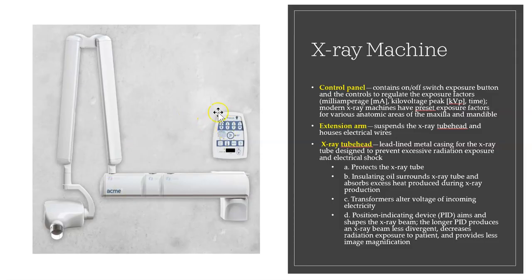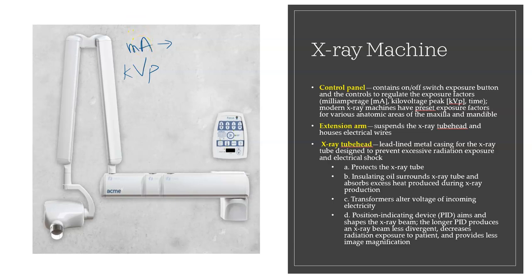When looking at the x-ray machine, there is the control panel where the on/off switch is. This is also where settings regulate exposure factors such as mA (milliamperage) and kVp (kilovoltage peak). mA controls density — increasing mA gives a darker image, decreasing mA gives a lighter image.